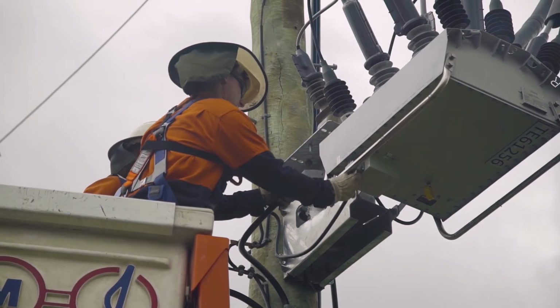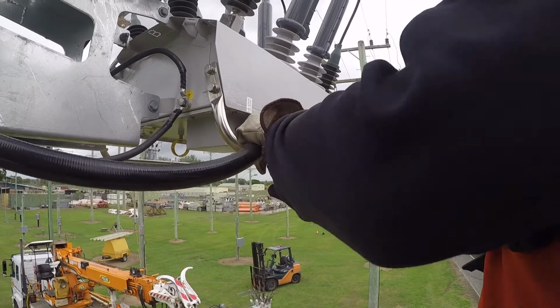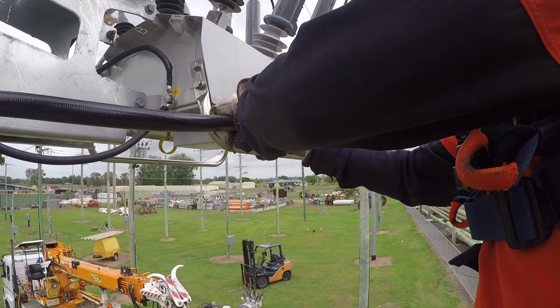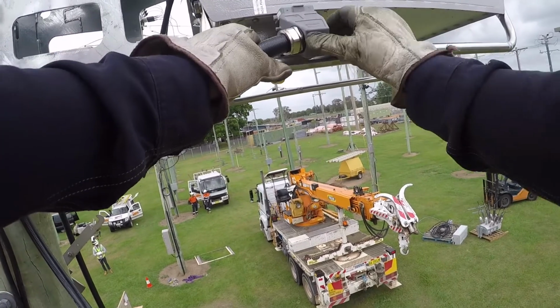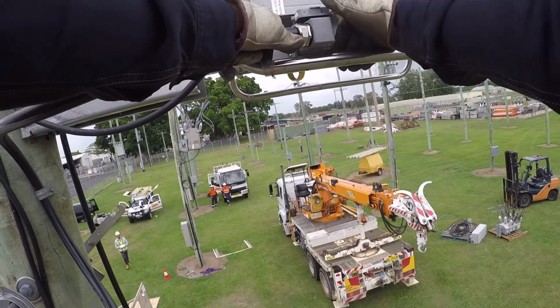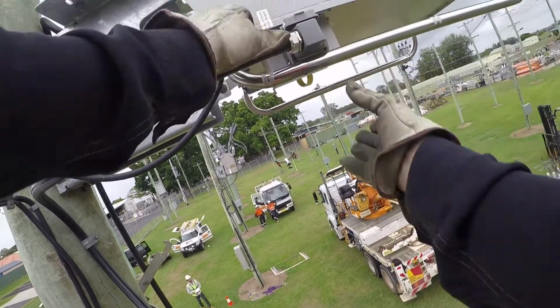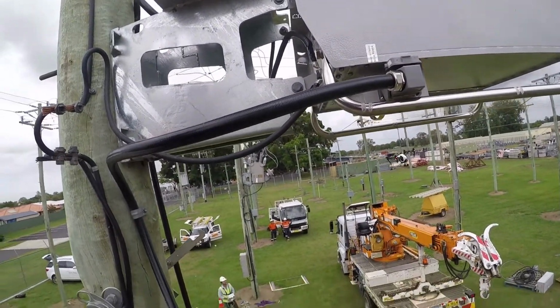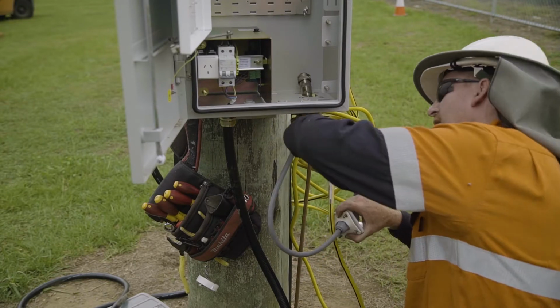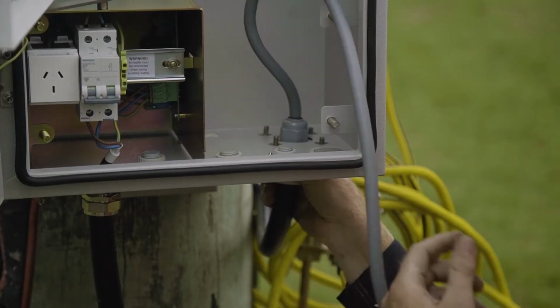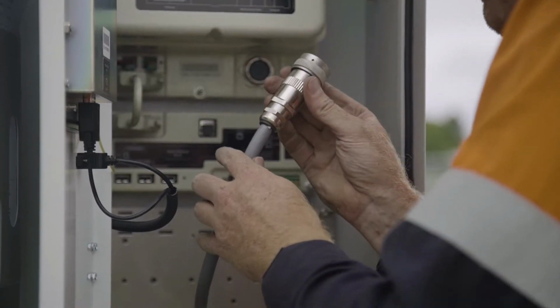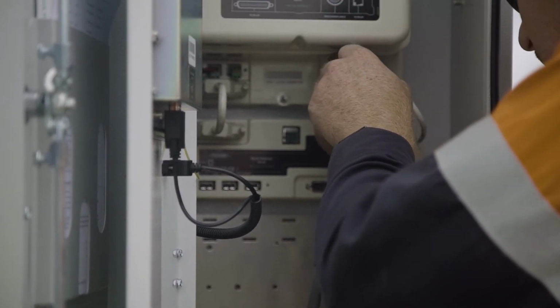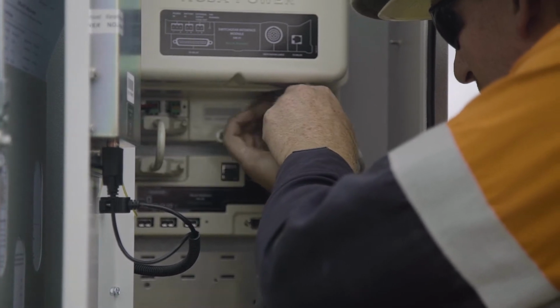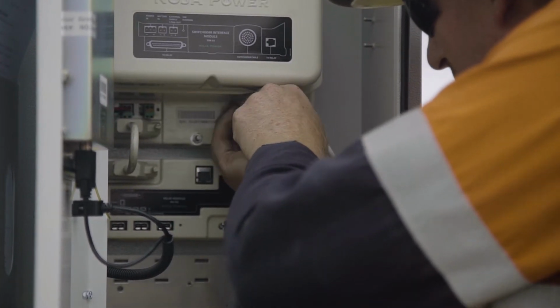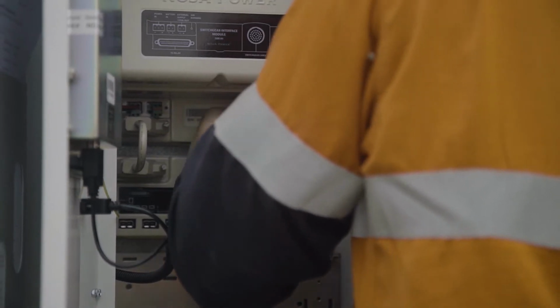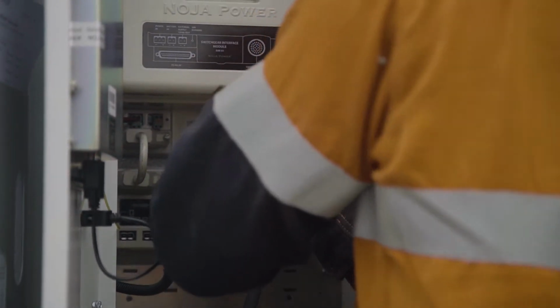The control cable is plugged into the tank and secured by lifting the latch until it clicks into place over the pins. Both sides must be over the pins or the cable will not be sealed against water entry. Fix the control cable to the pole using saddles at regular intervals. Slide the connector through the entry hole. Secure the vandal-proof gland using 4 wing nuts. Connect the control cable to the SIM module. Position the key and lock the nut by turning it clockwise until it snaps into place. Position the cable inside the cubicle, cable tie to the bracket if required.